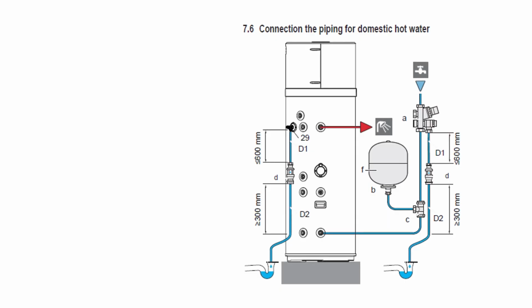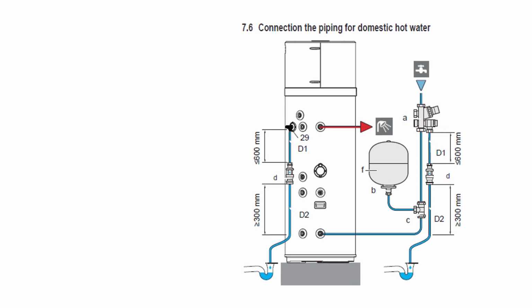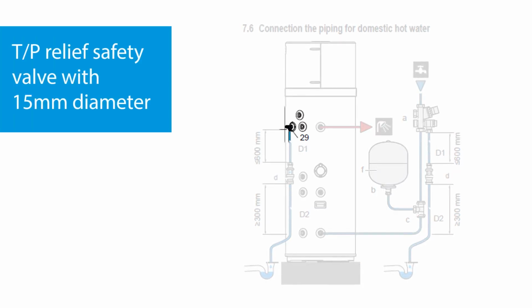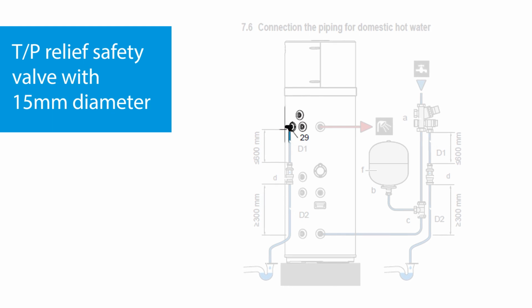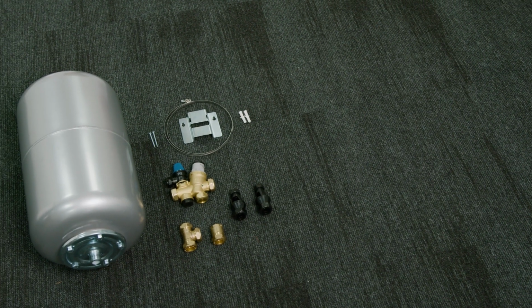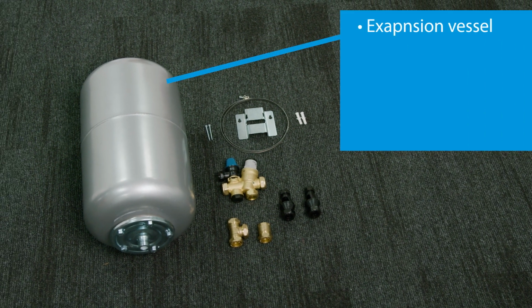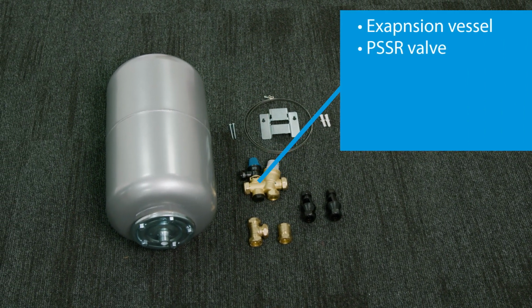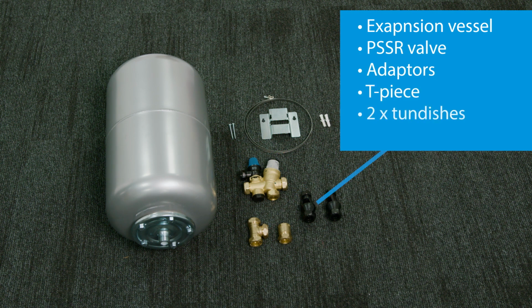The tank itself is enclosed in an ABS plastic enclosure and 50mm PUR insulation. Both features prevent heat loss. It is mandatory that the installation complies with Part G3 of the building regulations, the hot water supply and systems, which covers issues such as withstanding the stress of temperature and pressure increases through normal use. The unit is factory fitted with a temperature and pressure safety relief valve and is supplied with a G3 kit comprising an expansion vessel, pressure reducing or sustaining valve, adapters, T-piece and 2 tundishes.